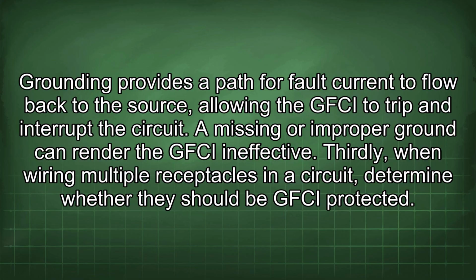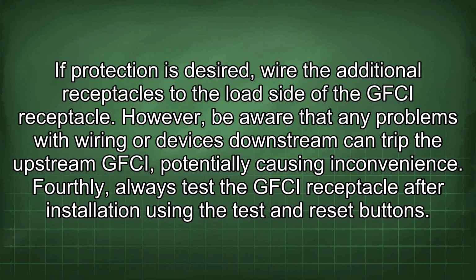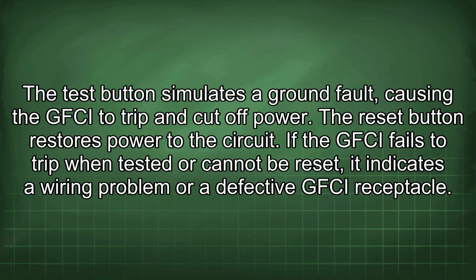Thirdly, when wiring multiple receptacles in a circuit, determine whether they should be GFCI protected. If protection is desired, wire the additional receptacles to the load side of the GFCI receptacle. However, be aware that any problems with wiring or devices downstream can trip the upstream GFCI, potentially causing inconvenience. Fourthly, always test the GFCI receptacle after installation using the test and reset buttons. The test button simulates a ground fault, causing the GFCI to trip and cut off power. The reset button restores power to the circuit.